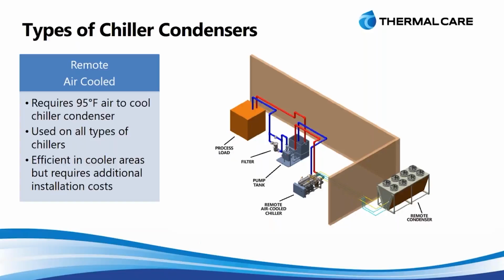But it does have the benefits that you can avoid glycol, and you're still discharging your heat outside. So there are benefits to all three, whether it's a water-cooled, an integral air-cooled, or a remote air-cooled. And you need to consider your exact facility's demands to best determine which way you want to go.